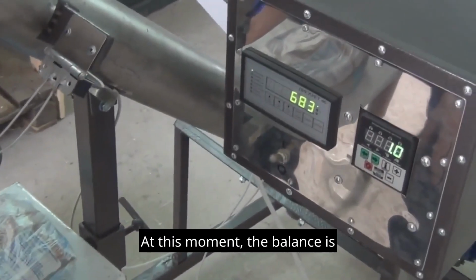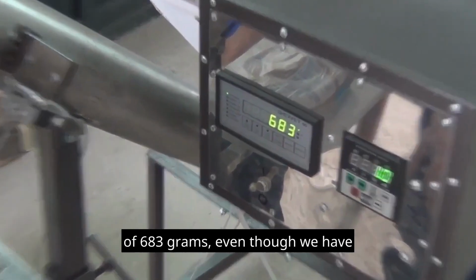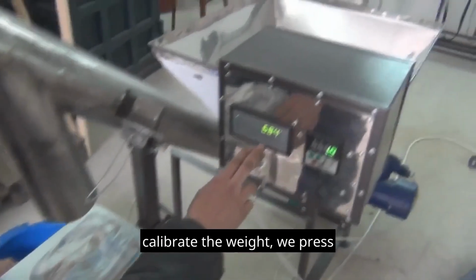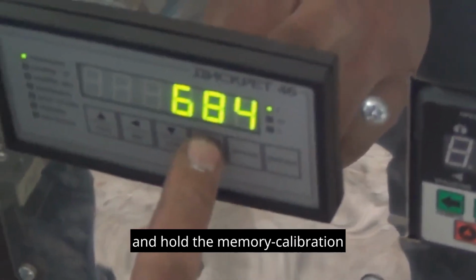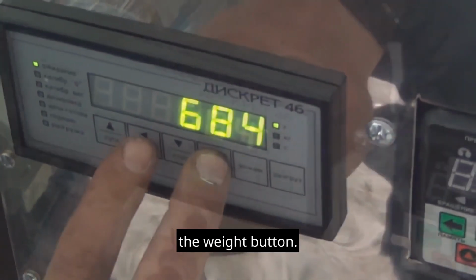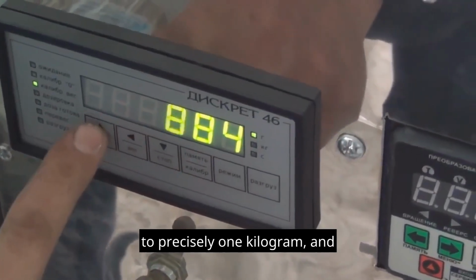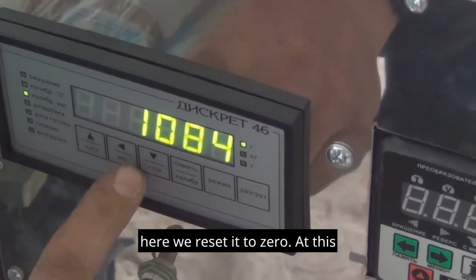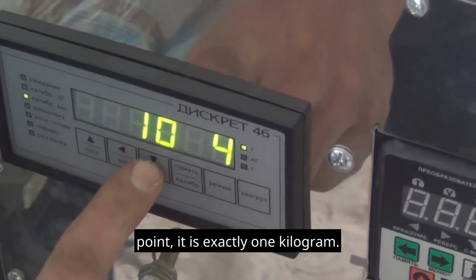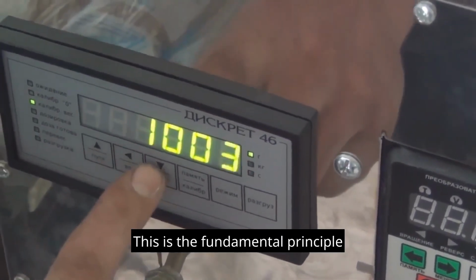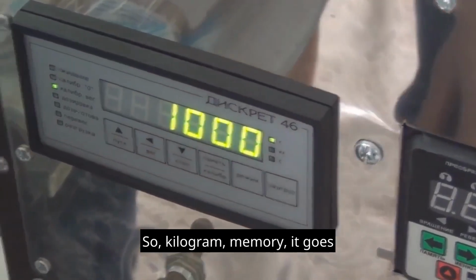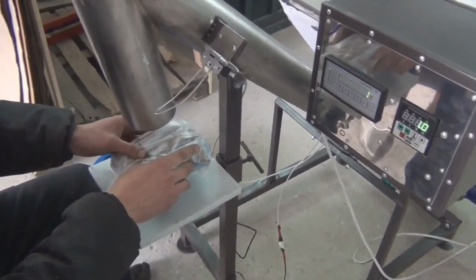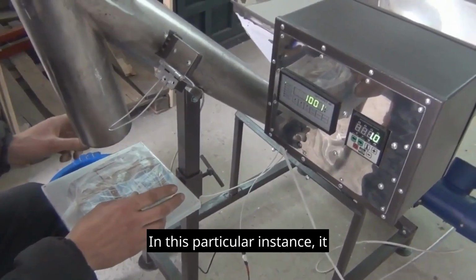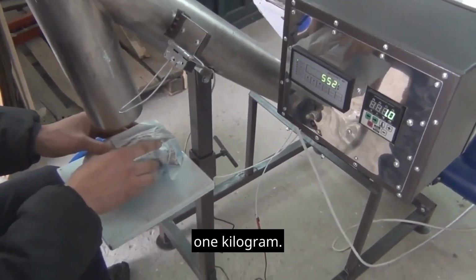At this moment, the balance is not calibrated, displaying a weight of 683 grams, even though we have a full kilogram here. To properly calibrate the weight, we press and hold the memory calibration button, and then press the weight button. In this instance, we adjust it to precisely 1 kilogram, and here we reset it to 0. At this point, it is exactly 1 kilogram. This is the fundamental principle of weight calibration. So kilogram, memory, it goes into standby mode. It's now a kilogram, not 600 grams. In this instance, it shows precisely 1 kilogram.